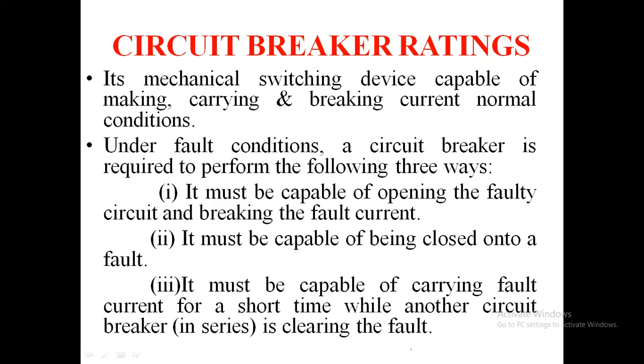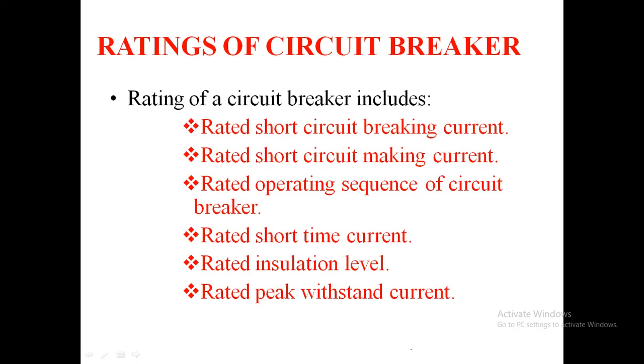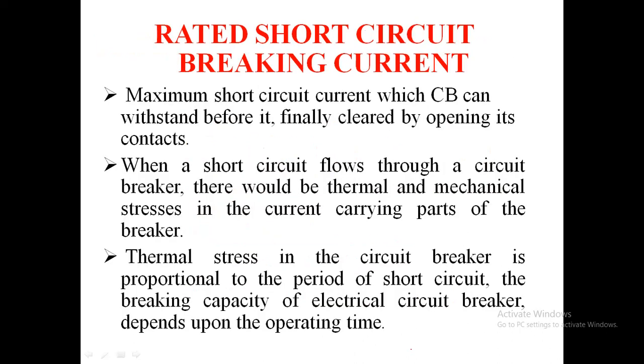Suppose under fault condition we have to perform in three different ways. One is to be capable of opening the fault circuit and breaking the fault current. Another is to be closed onto the fault. And it must be capable of carrying the fault current for a short time while another circuit breaker in series clears the fault. These are some of the ratings of a circuit breaker: rated short circuit breaking current, short circuit making current, sequence, short time current, insulation level, peak withstand current. We will see them elaborately in the next slide.